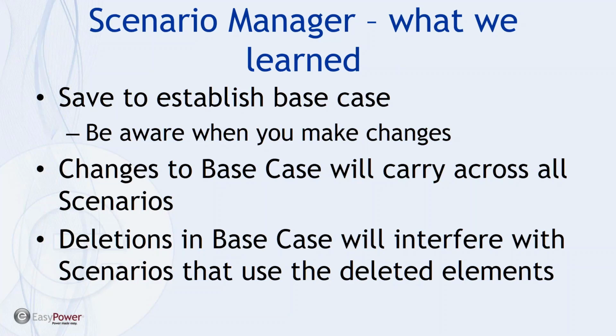It says, is there a way to enter transformer tolerances positive for load flow and negative for short circuit? That's a good question. I haven't tried it. My first reaction is that it's a good exercise to take on as a personal challenge, and that is to create one base case with transformer tolerances in. So the question is load flow. The answer is, I believe, yes, that I can use scenarios for load flow. The reason I say that with a fair amount of confidence is that the Scenario Manager primarily was developed for load flow comparisons, and I will try that offline and then send out the results via email to anyone that's attended the webinar.